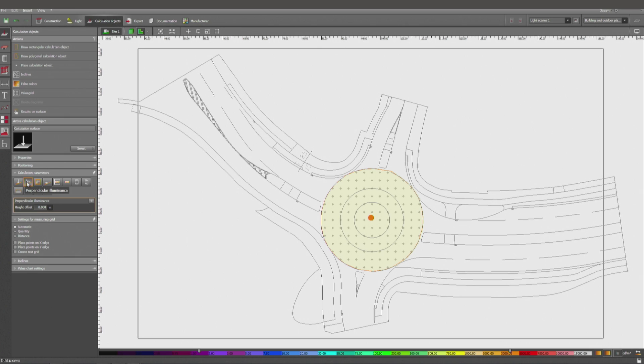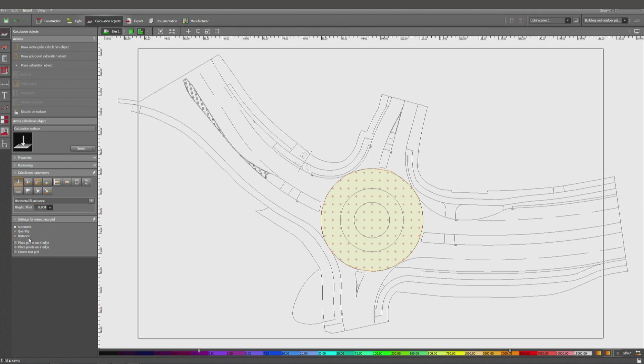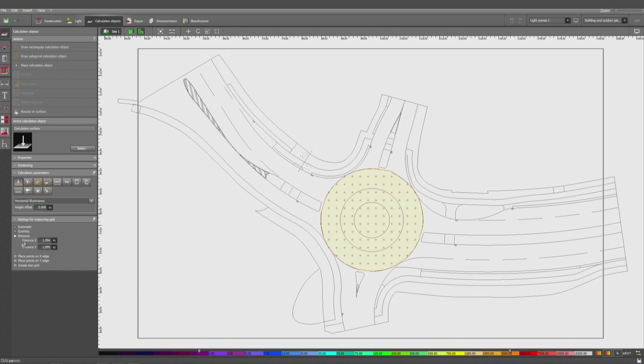Here we are going to determine the type of calculation we want to do. It's not the perpendicular illuminance but the horizontal one right on the floor, so we're zero centimeters offset. The distance we have to determine - it should be one tenth of the shortest distance between two poles.